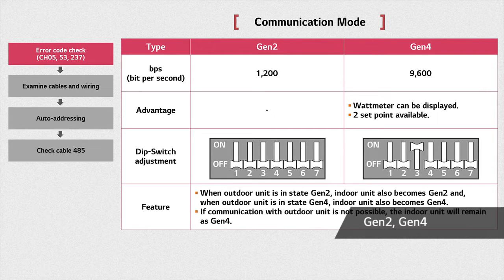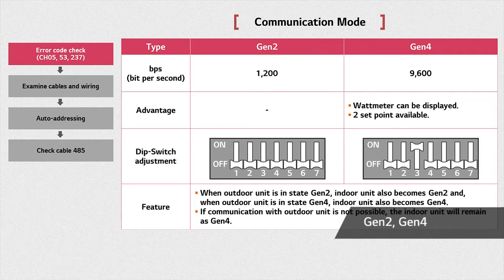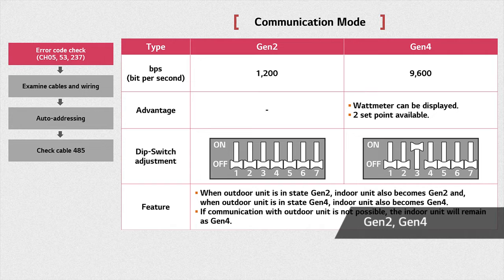To activate Gen2 mode at the ODU, DIP switch number 3 should be off, and for Gen4, it should be on. The difference between these two modes is that through Gen4, you can see the wattmeter from the indoor unit, and the two set points function is also available.